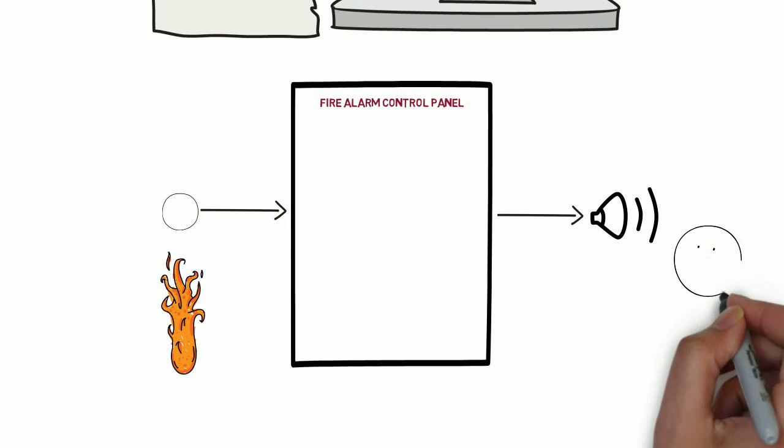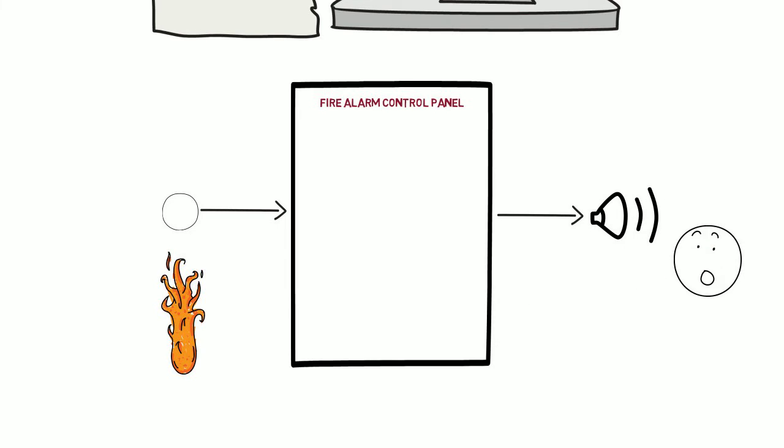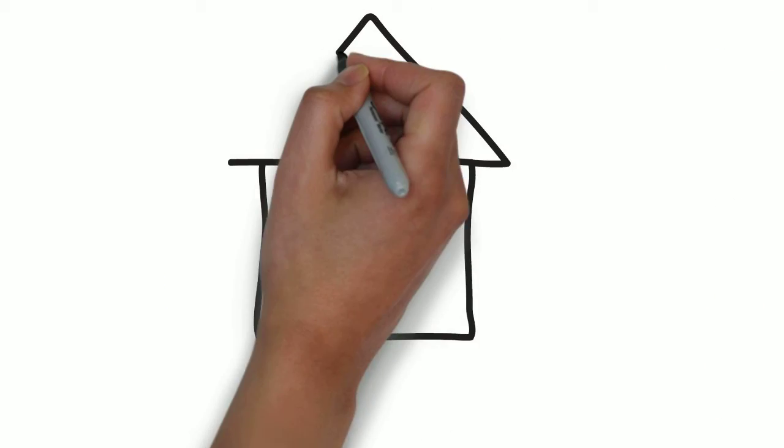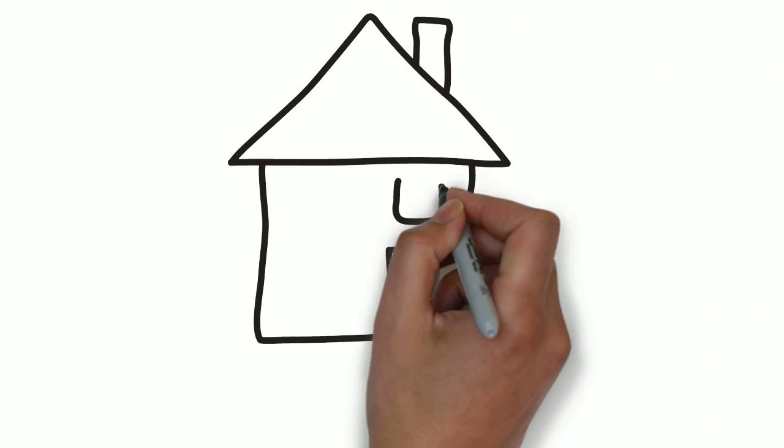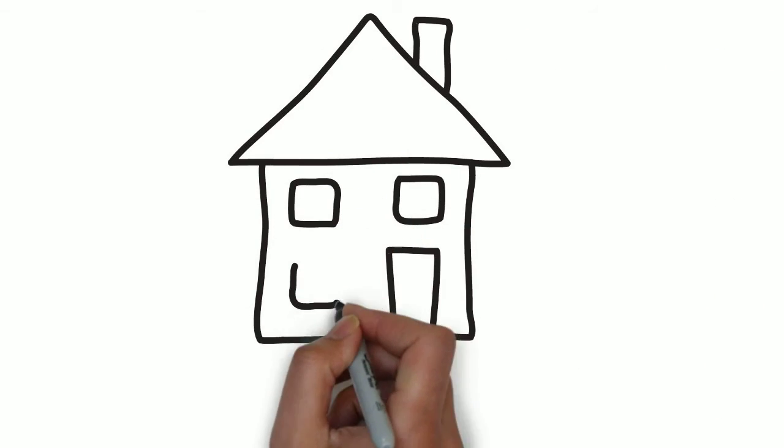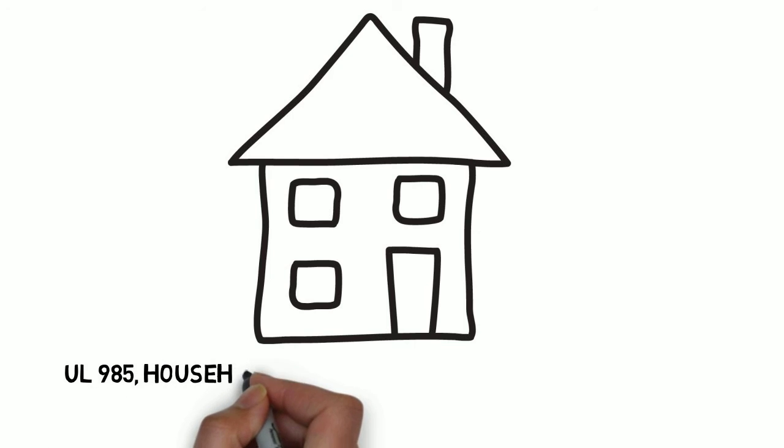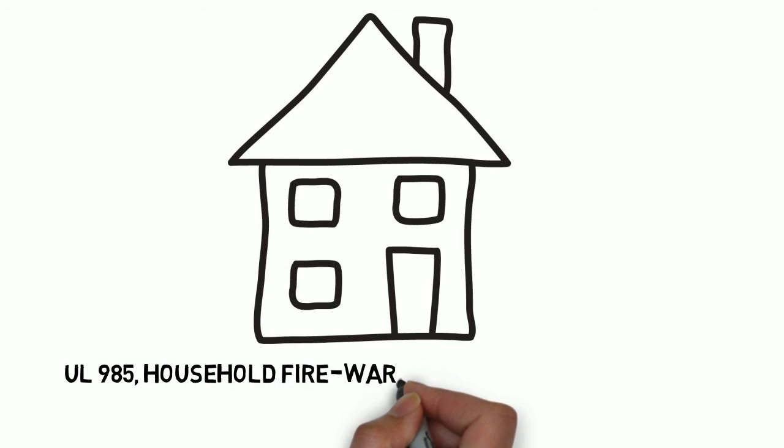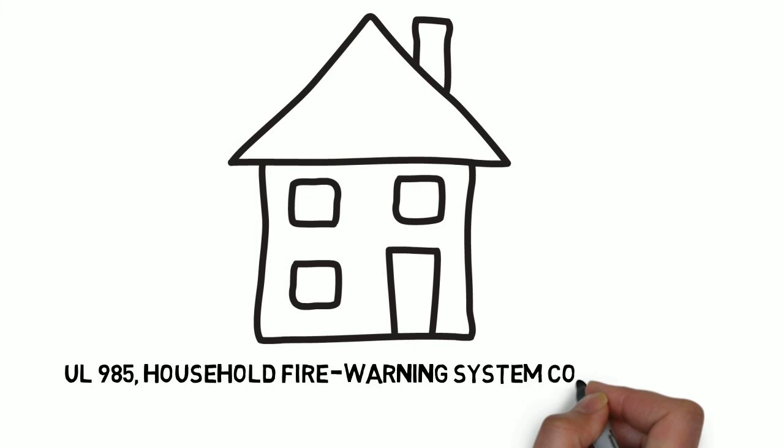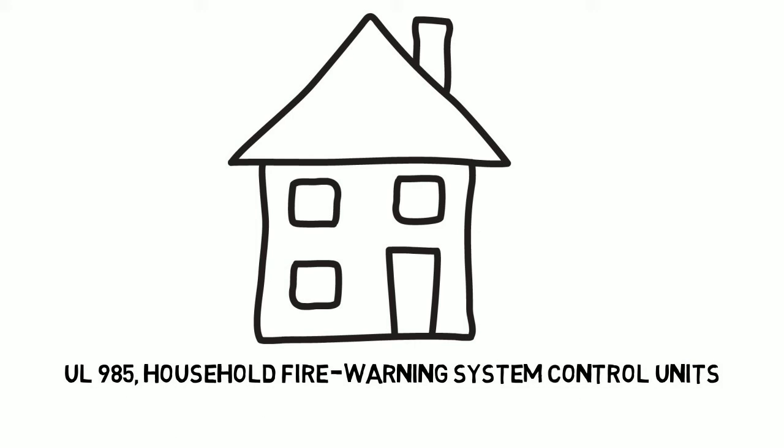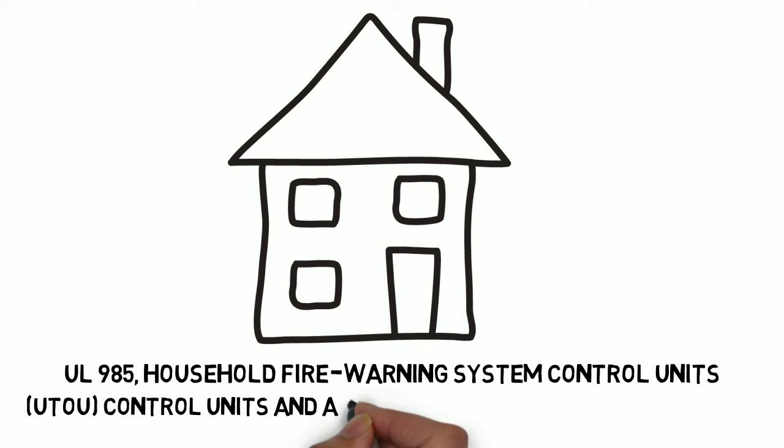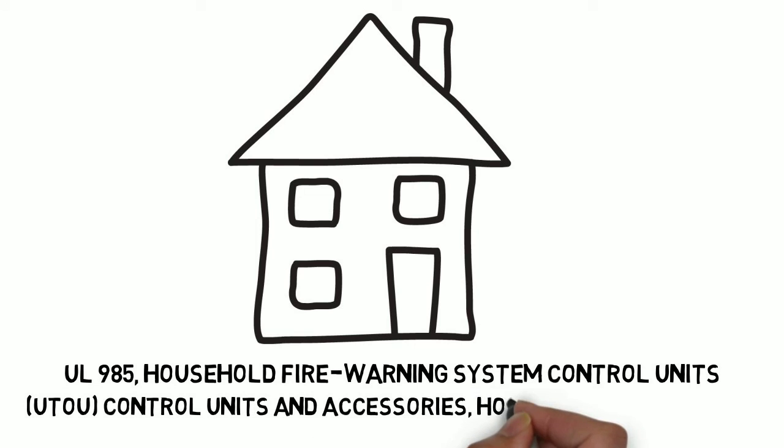When intended for installation in a house or any dwelling, the fire alarm control unit is investigated to UL 985, Household Fire Warning System Control Units, and listed under the product category UTOU, Control Units and Accessories, Household System Type.